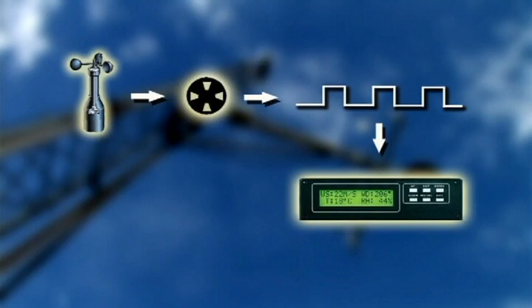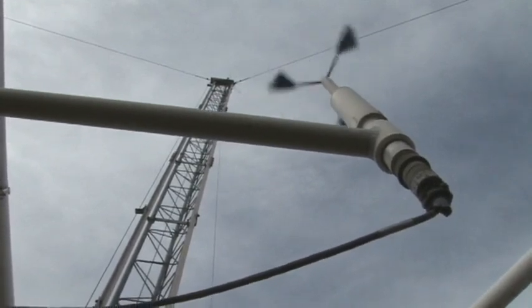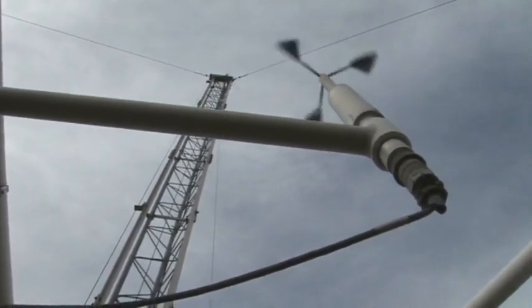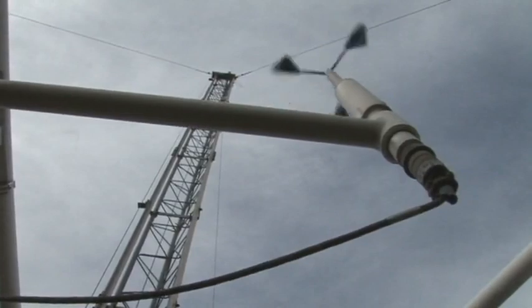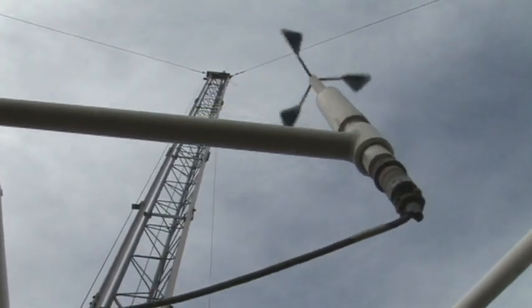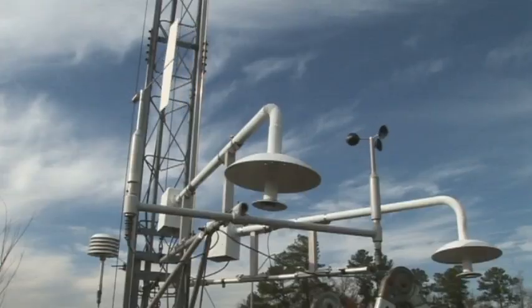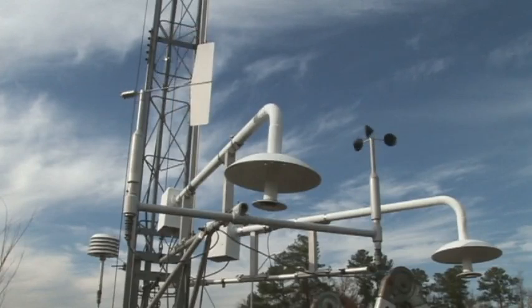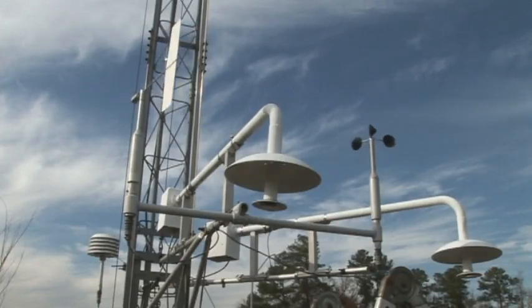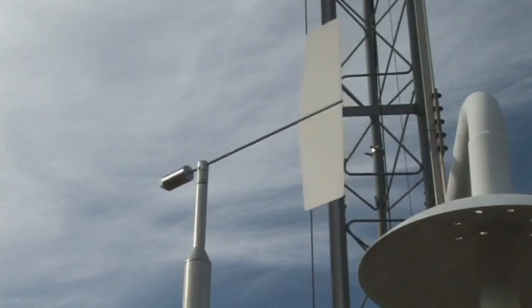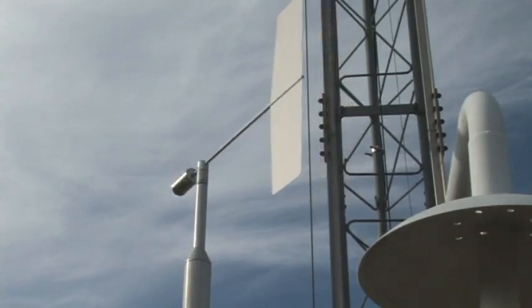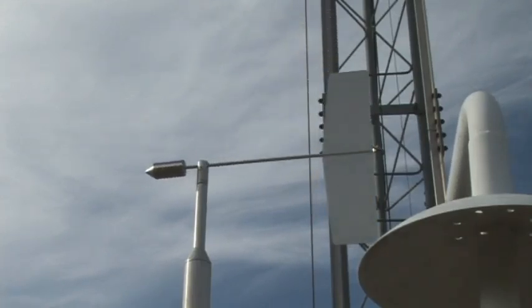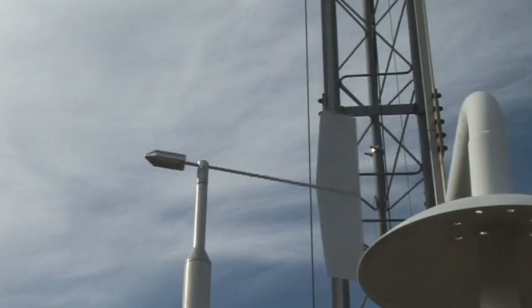So if we spin the sensor at a known speed, it should translate to a value in the translator and be recorded by our data acquisition system, also known as our DAS. This second sensor is a wind direction vane. It works on a simple principle of a sweeping potentiometer. The internal potentiometer is wired in a way that its position will determine the voltage that is sent to the translator. Each voltage corresponds to a different wind direction.